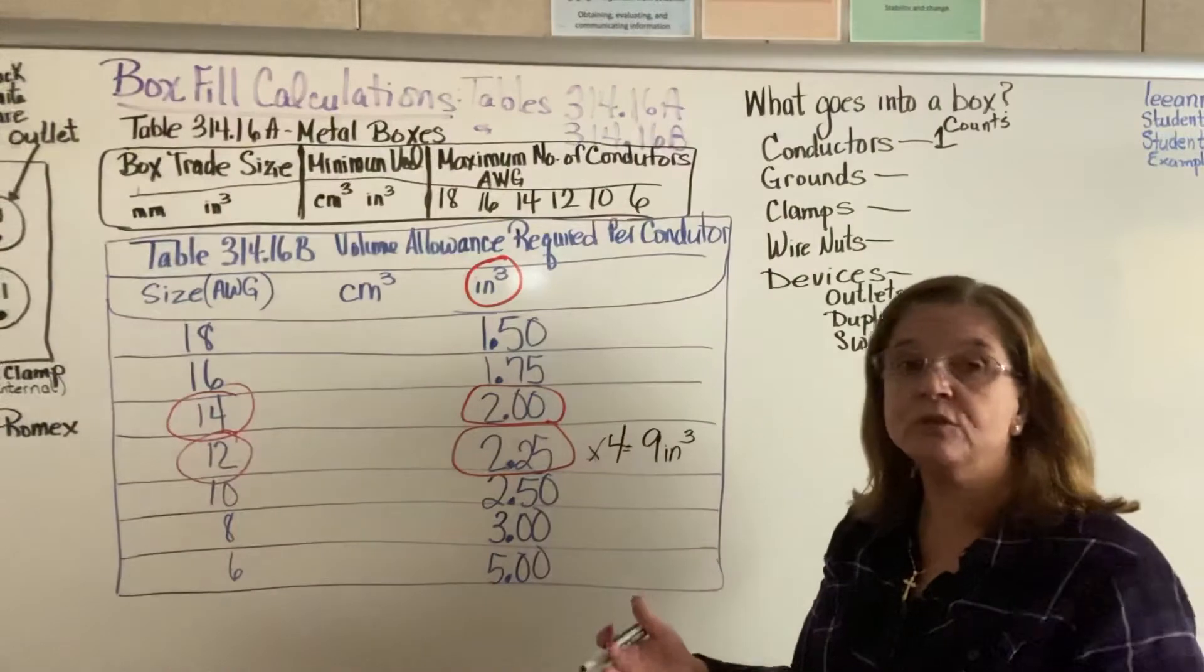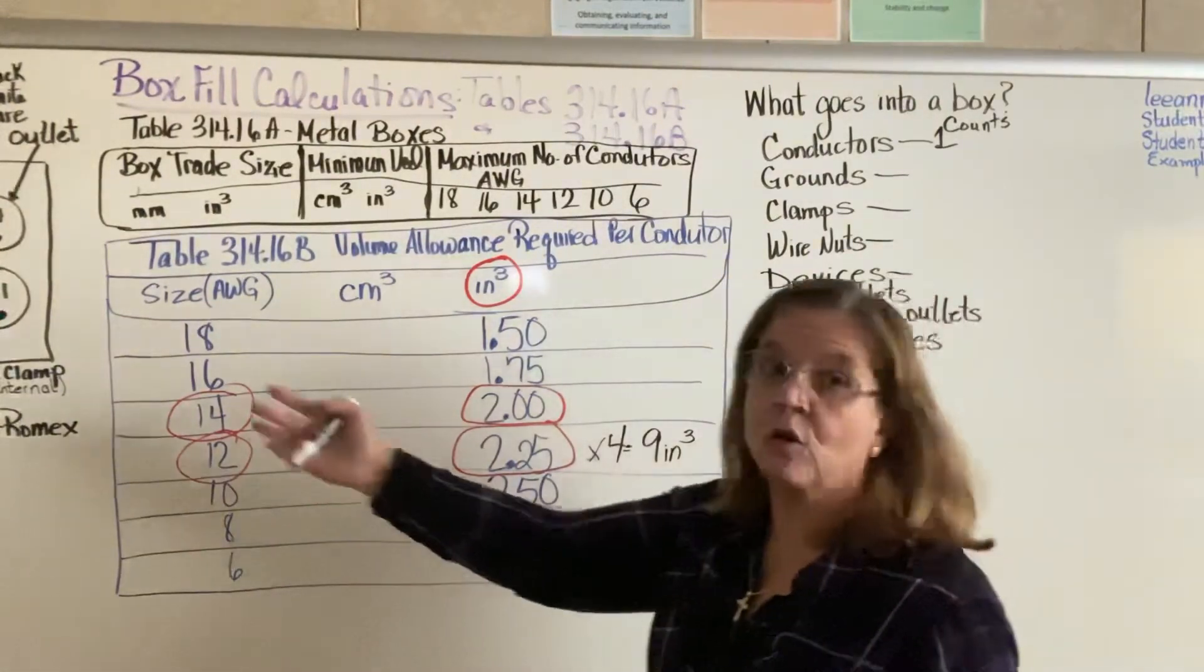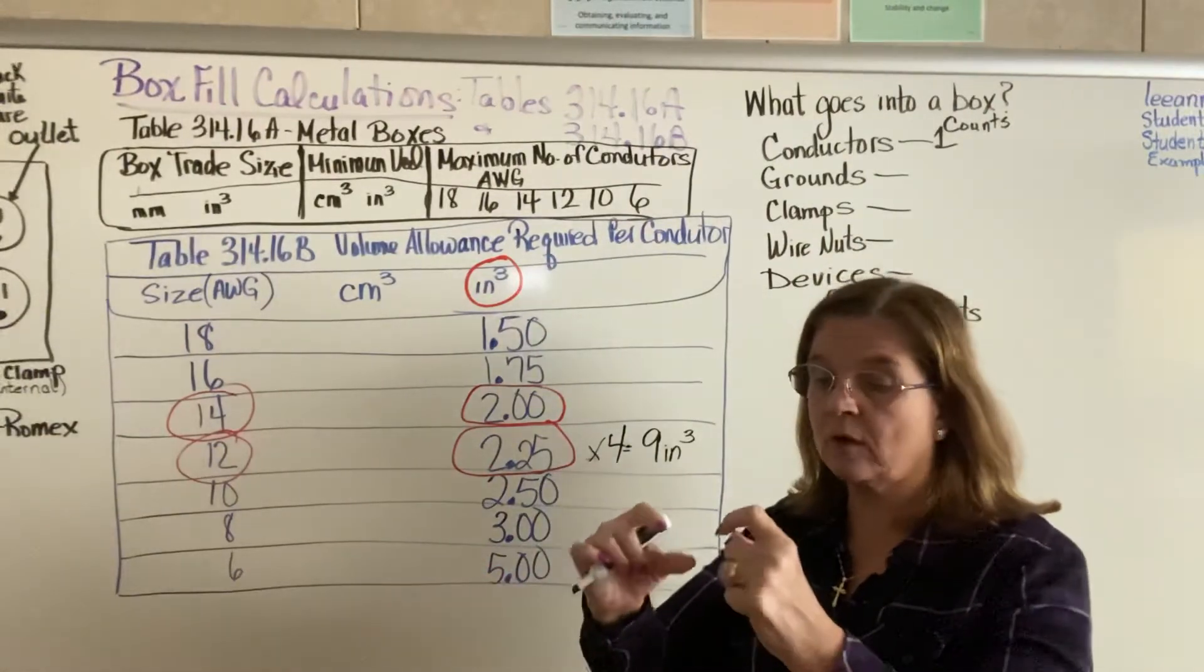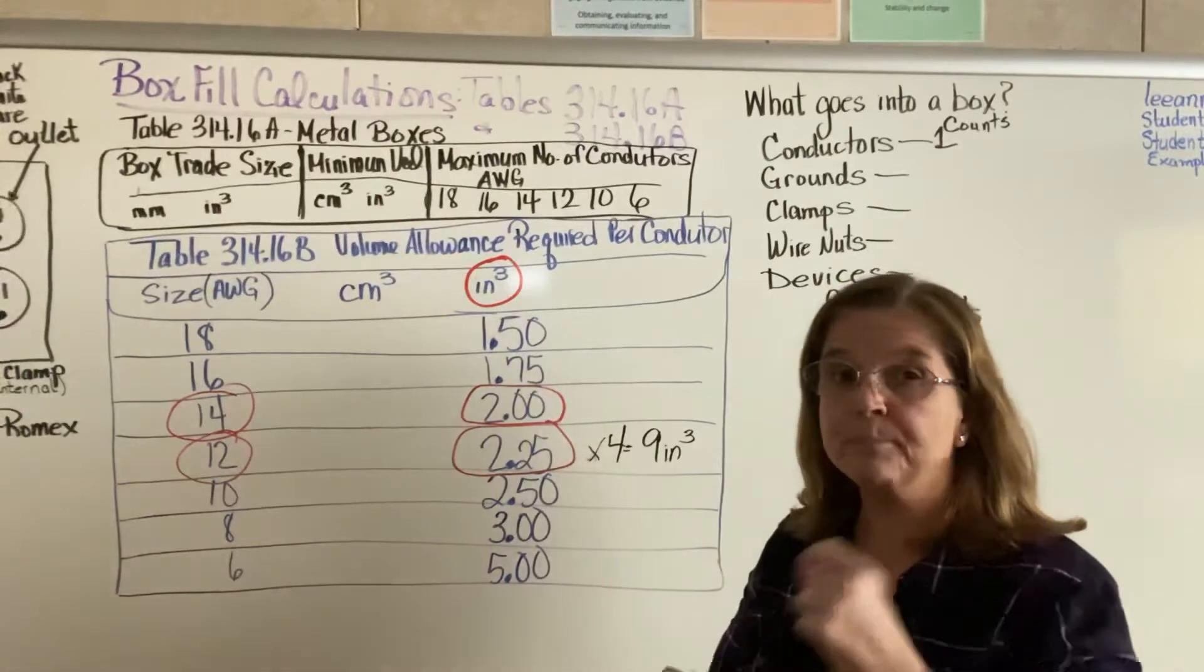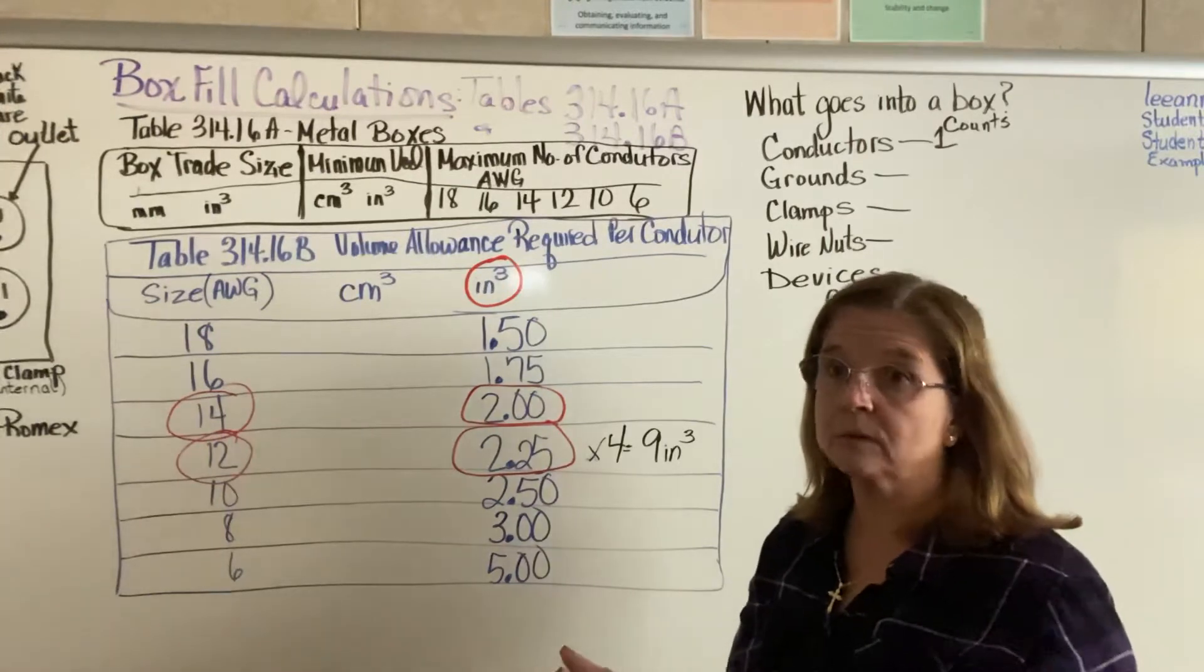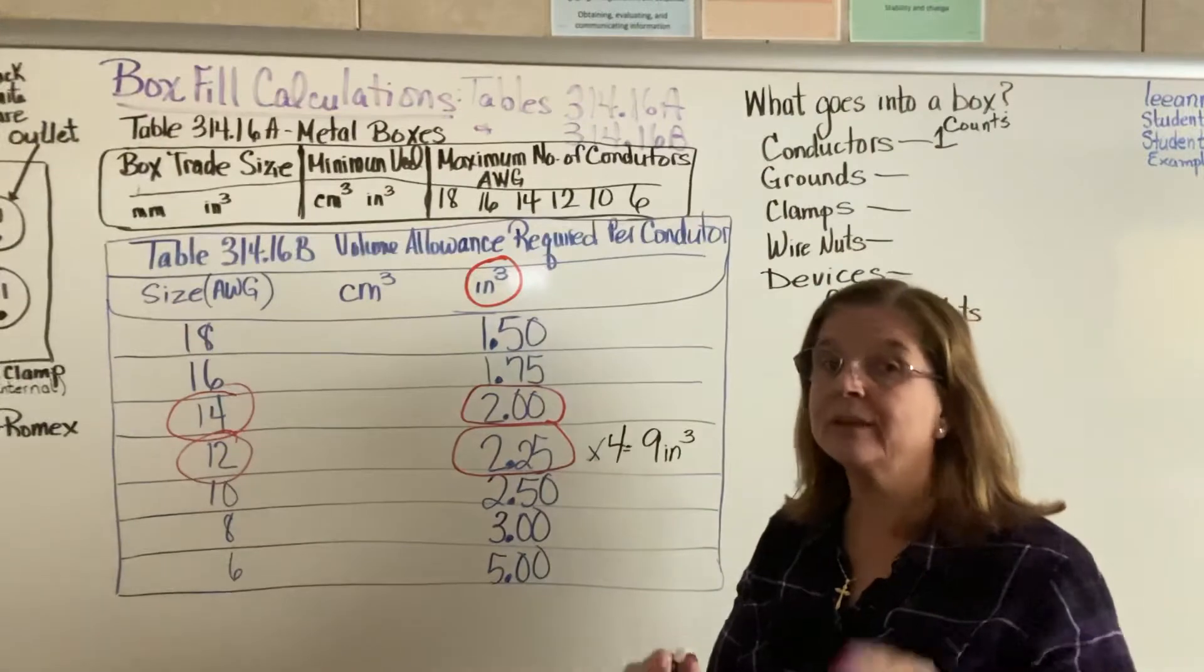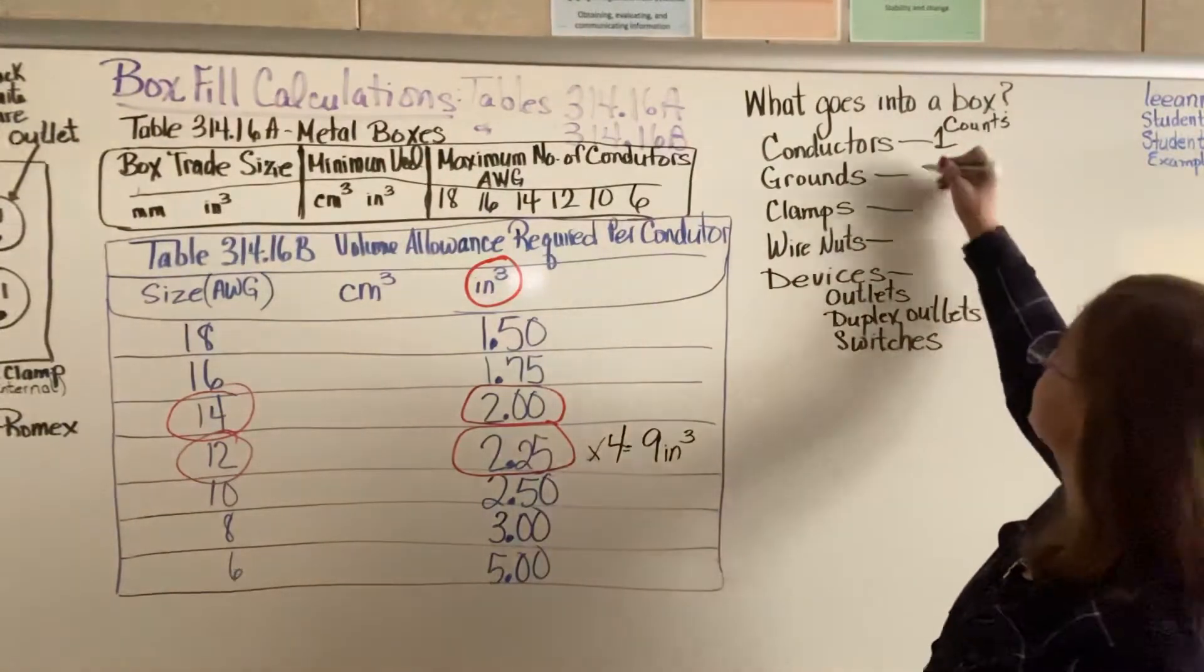You now have to use grounds. The grounds automatically come in the Romex. If you peel back a Romex, you will see there are three pieces of wire in there: a black, a white, and a bare wire. The bare colored wire, or the one with no covering, is the ground. No matter how many grounds you have in there, the grounds count only once. You pick the largest ground.